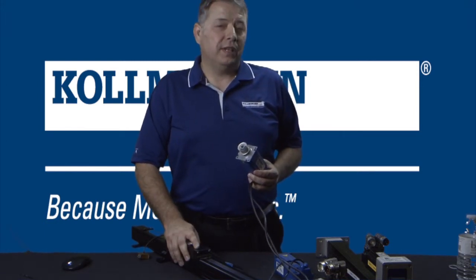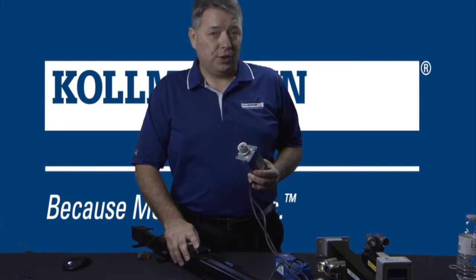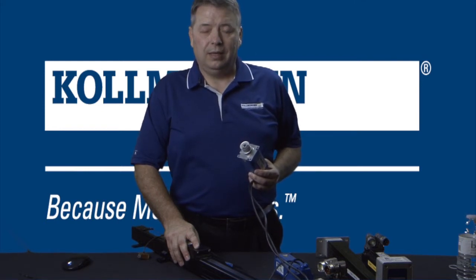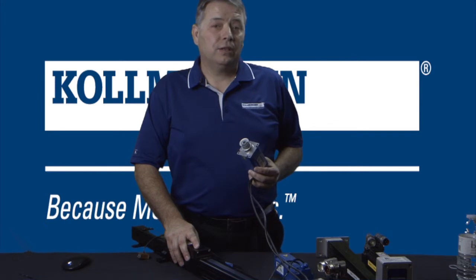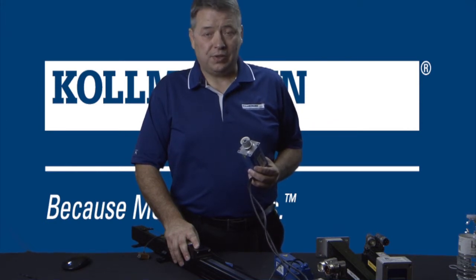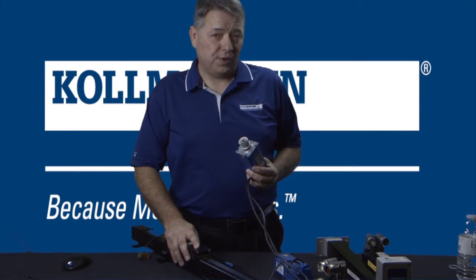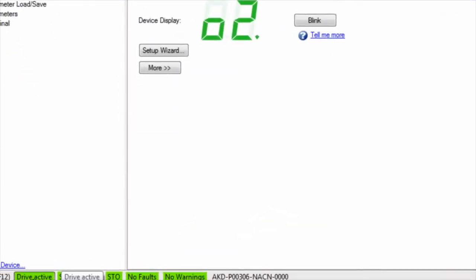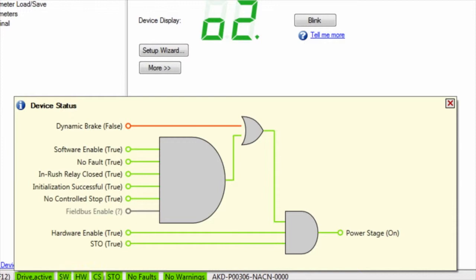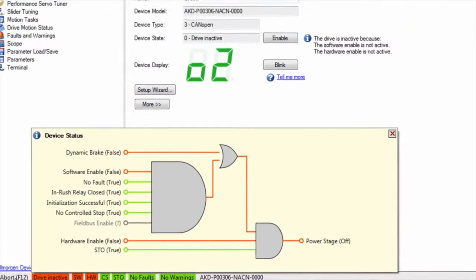This segment is on the AKD Scope tool advanced use and is part 3. In this segment, we will be taking a closer look at different trigger methods and when we might use these different methods to help us troubleshoot a system. Sometimes it is helpful to capture data when the drive is active or more when the drive is deactivated, such as when a fault occurs.